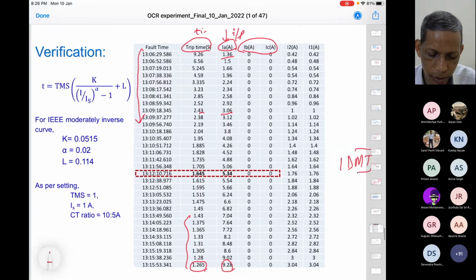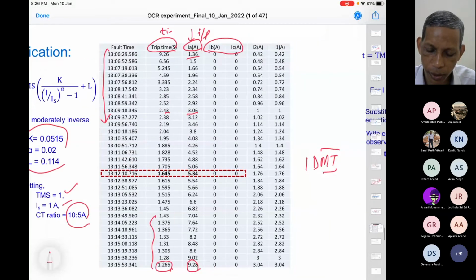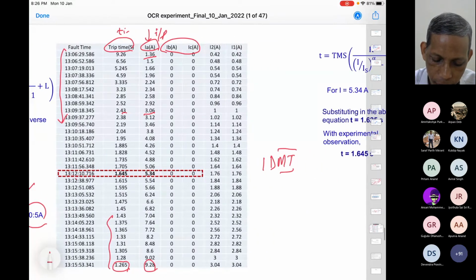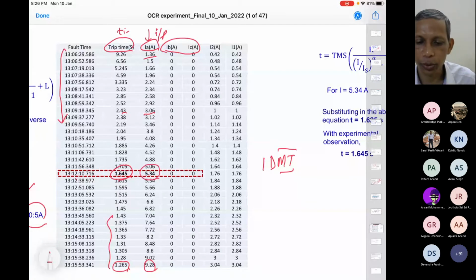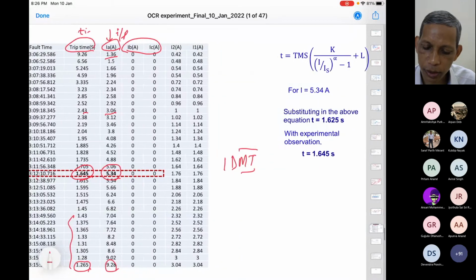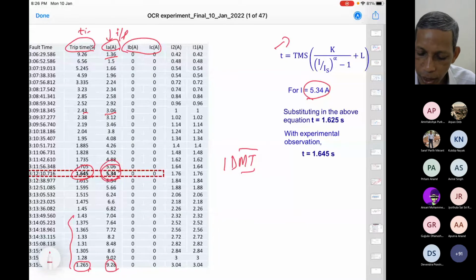As I say, these are the constant terms. TMS is 1, the IS setting is 1 ampere, and CT ratio is 10:5. We are scaling down by a factor of 2 only. Fine. So for example, here the time is 1.645 for an injection current of 5.34. Using this equation, this curve, if you substitute the data L, K, alpha and so on, then for a 5.3 ampere input the calculated time is 1.625.